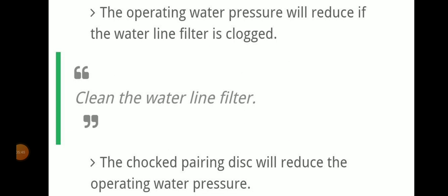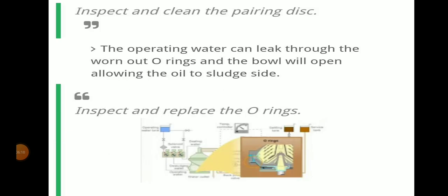The choked pairing disc will reduce the operating water pressure. Operating water pressure will reduce if the water line filter is clogged. Clean the water line filter. Choked pairing disc will reduce the operating water pressure. Inspect and clean the pairing disc.